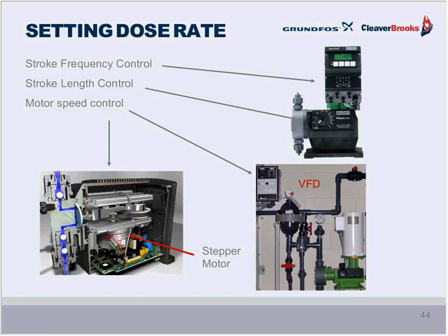In order to treat water for the boiler system, we need to control the flow rate. So next, let's take a look at how we set those feed rates or dose rates of the metering pump. Now, these are reciprocating positive displacement devices, so with each stroke they move a very specific amount of fluid. We control the pump feed rate with a combination of stroke frequency, stroke length, and motor speed adjustment. As stroke frequency increases, we are drawing in and pushing out more chemical over time, in strokes per minute. The longer the stroke, the more volume is displaced each time, and so we realize an increase in feed rate. Motors with a VFD, or in the case of a stepper motor, directly affect strokes per minute also.